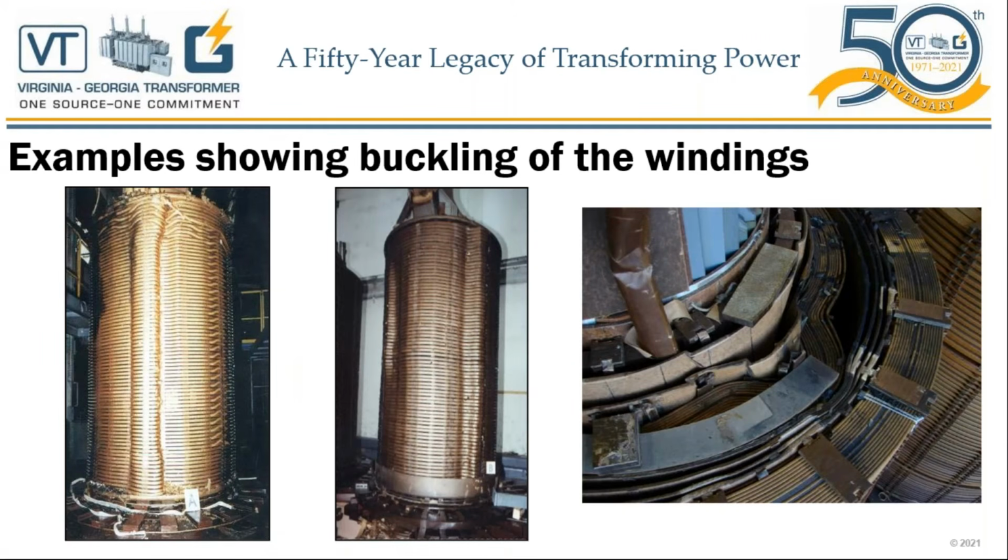Let us look at some examples showing buckling of the windings. These are some ugly examples from the industry. I don't know who the supplier is. It's not the point of the discussion here. But the point is for us to share this experience with you all in this webinar. So if you look at the left picture and the middle picture, it is very typical, and of course the right one too, but the view is different.